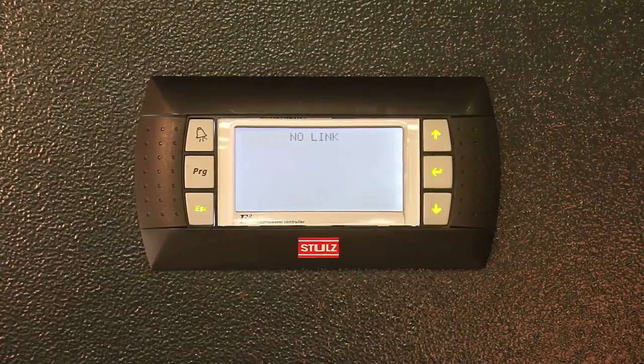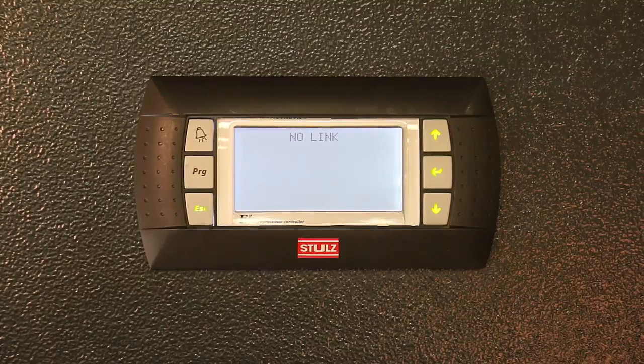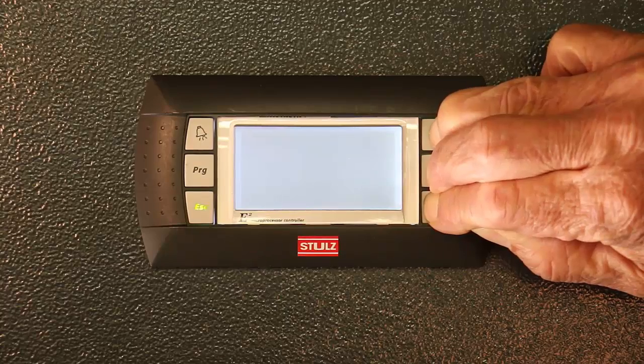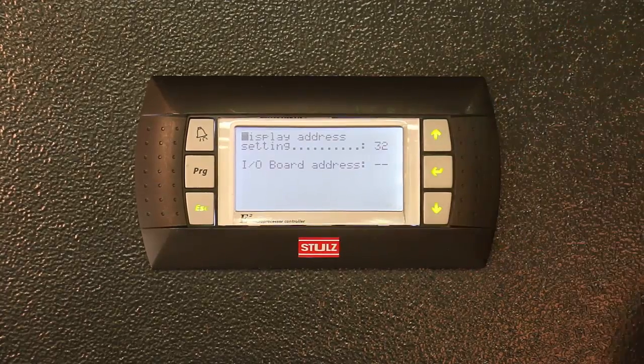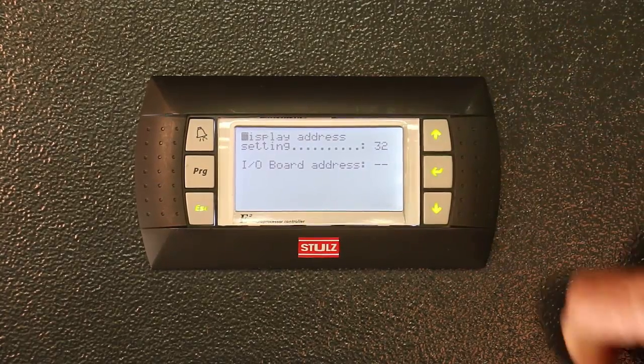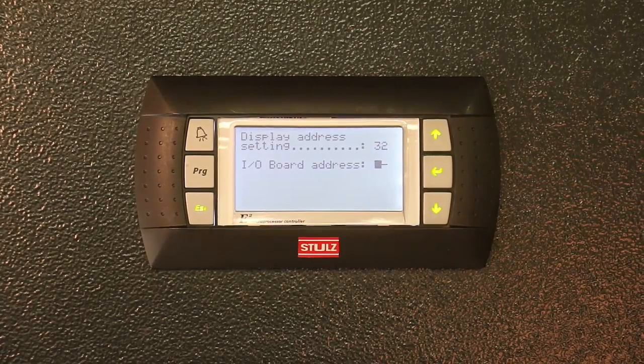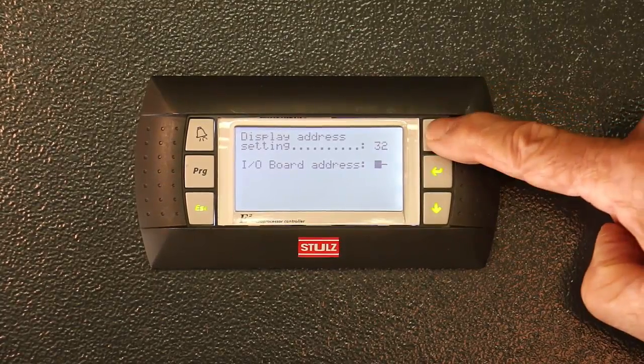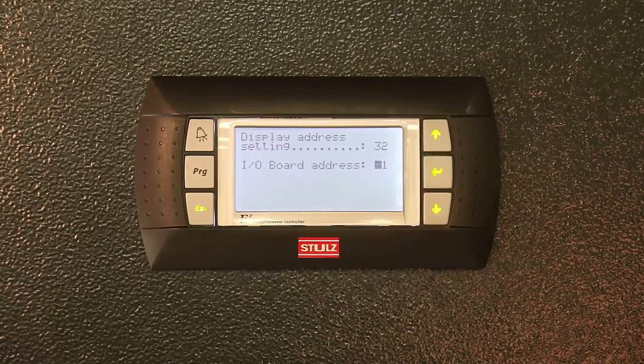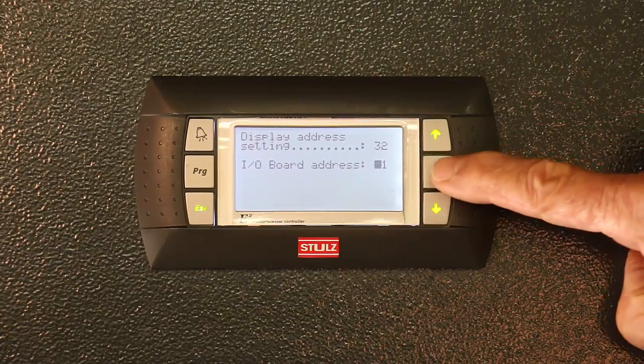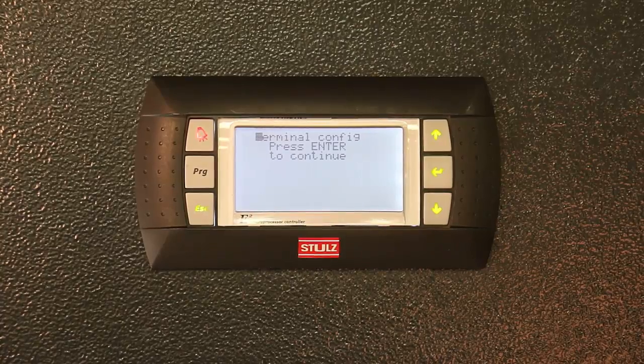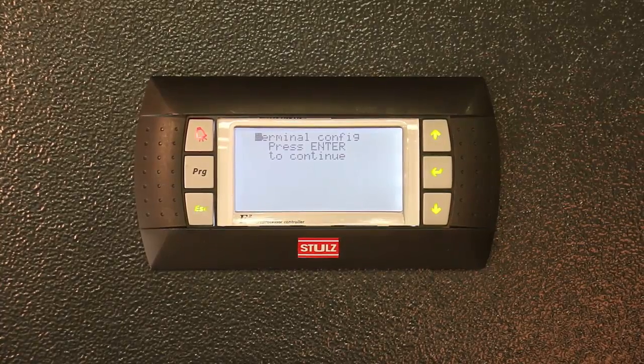'No link' will appear on the display. We will again press the up, down, and enter keys together. Press the enter key twice to move the cursor into position. Change the I.O. board's address by using the up arrow key to make your desired selection. The words 'terminal config — press enter to continue' will appear on the display. Press enter to continue.